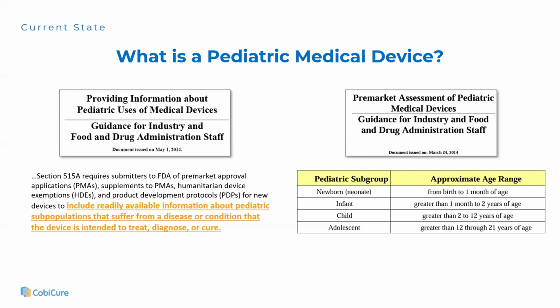So first, what is a pediatric medical device? FDA defines the pediatric population as from birth up until your 22nd birthday. Keep in mind that the 18 to 21-year-old age range is going to be important in some subsequent conversations. FDA has put out a couple of guidances around pediatric medical devices and their use. The guidance on the left is pertinent to high-risk therapeutic devices, typically class 3, that go through the pre-market approval process, or PMAs, or humanitarian device exemption, HDEs.